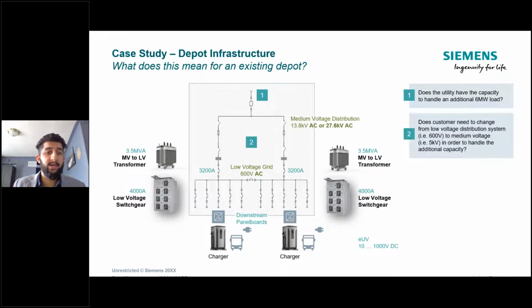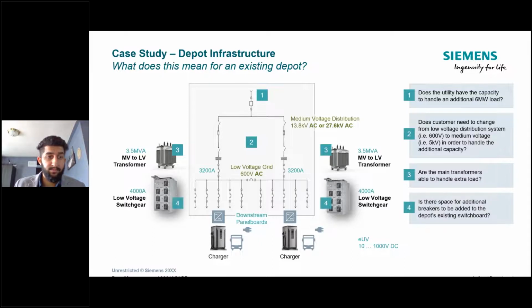You'd need to determine whether your existing infrastructure is enough or whether you'd have to upgrade to a medium voltage system to handle the additional capacity. You'd have to look at your current transformers and determine if they're able to handle the extra load. If not, you'd have to upgrade or add more transformers. You'd also have to determine if there's space for additional breakers on the existing switchboard, and if not, you may have to upgrade your switchboard or its quantity.